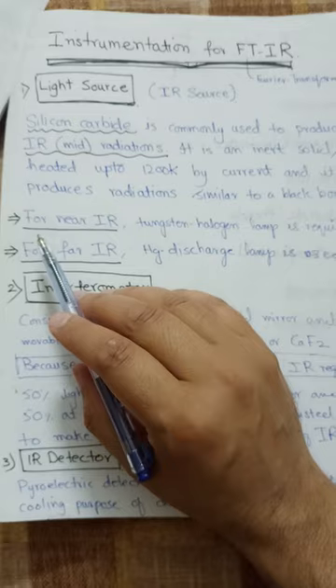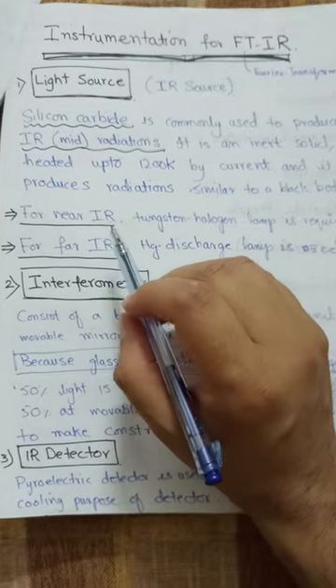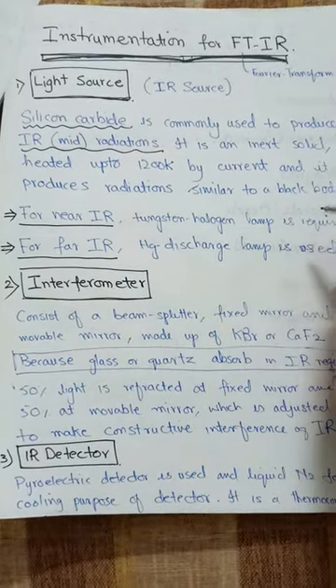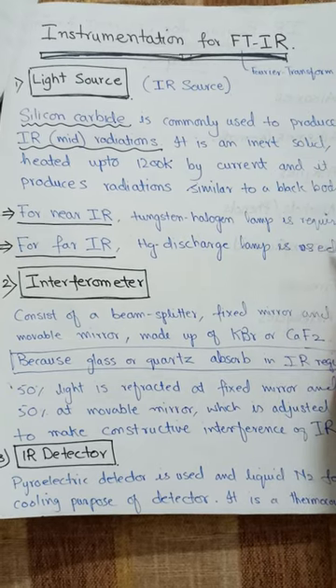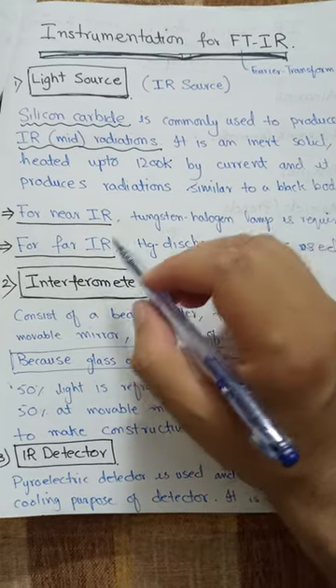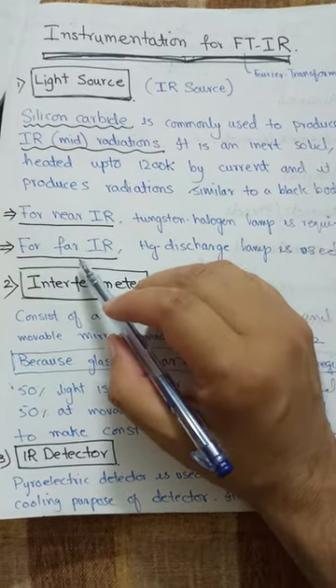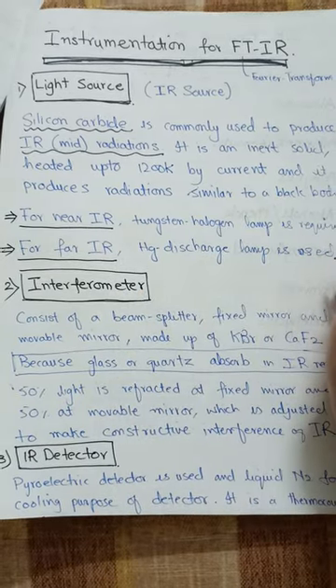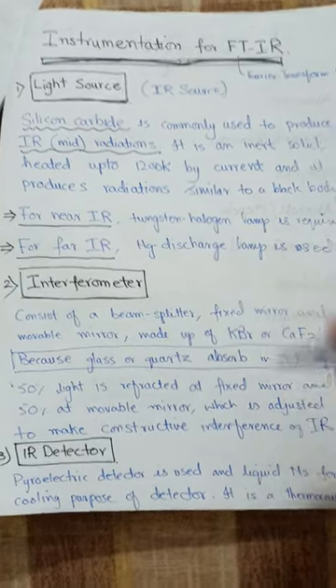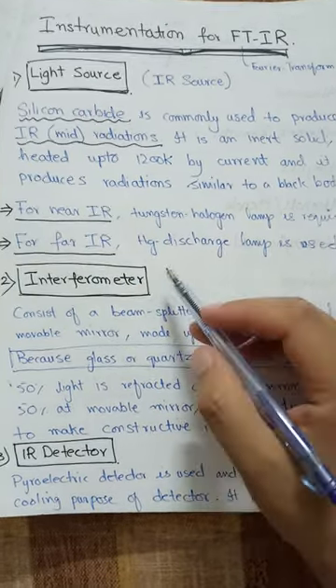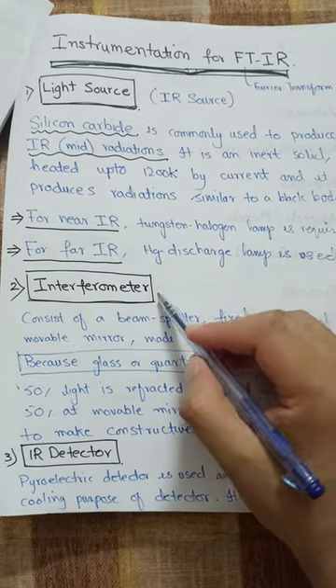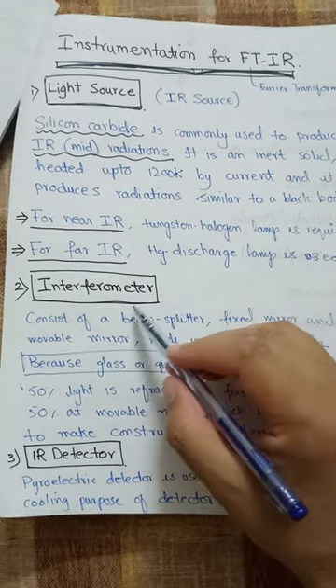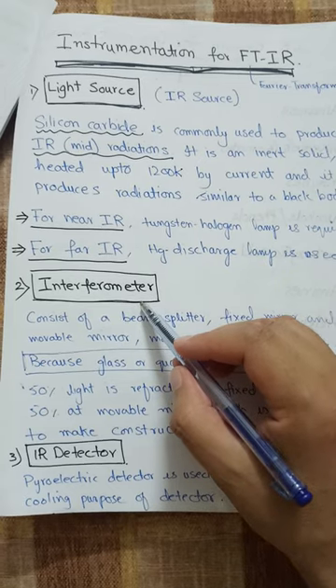For the near-infrared region we use a tungsten halogen lamp, and for the far-IR region a mercury discharge lamp is used. The second most important component of the IR spectrophotometer is the interferometer.